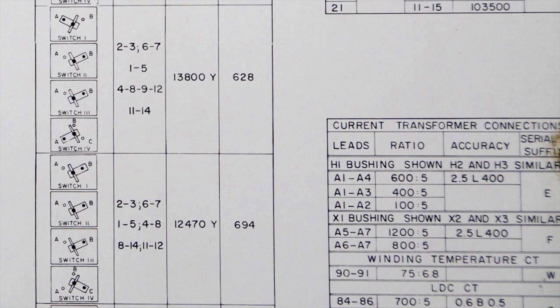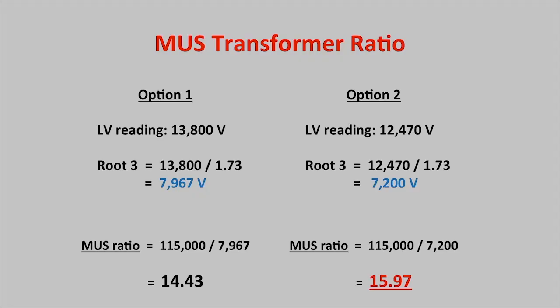To determine the MUS transformer ratio, you must first calculate root 3 of your voltage selection options. Root 3 of 13,800 is 7,967. 13,800 divided by 1.732 equals 7,967. And root 3 of 12,470 is 7,200. 12,470 divided by 1.732 equals 7,200.